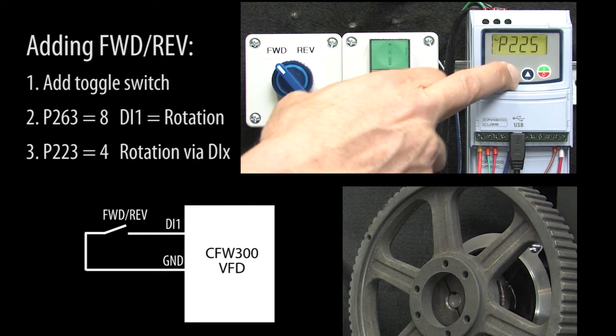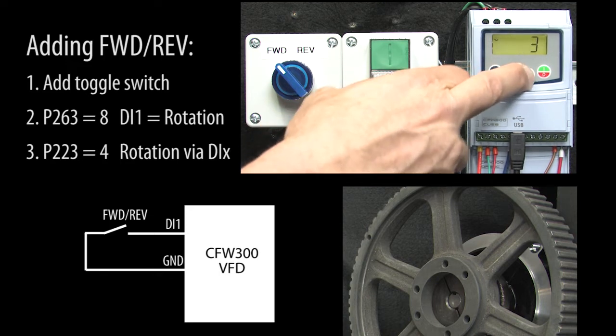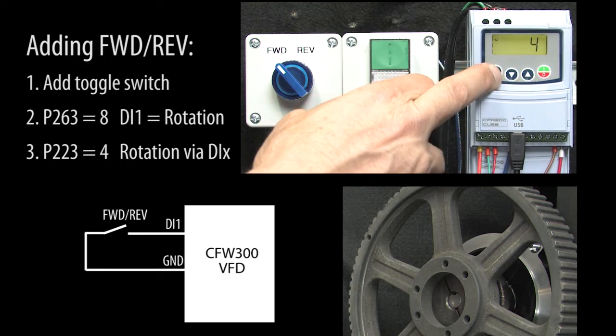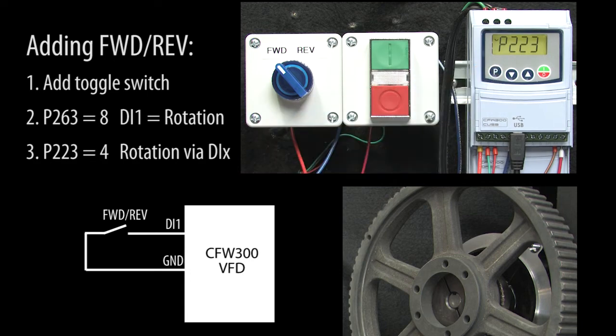Finally, go to parameter 223 and set it to a 4. That tells the drive that the rotation direction will be controlled by a digital input.